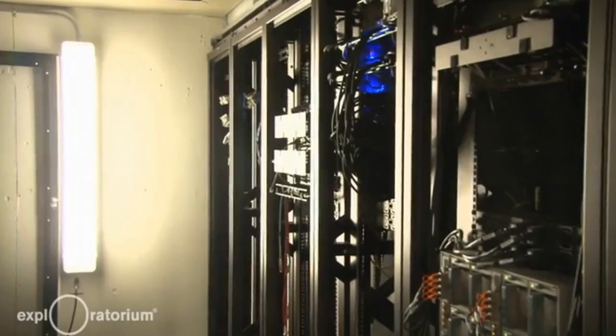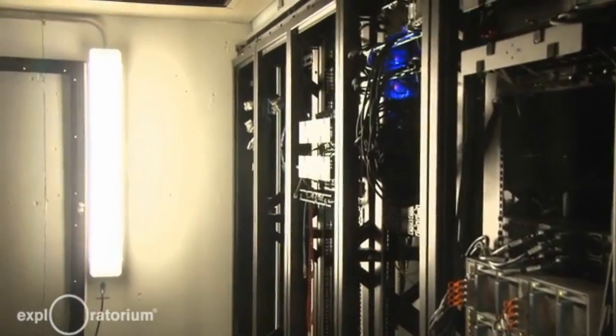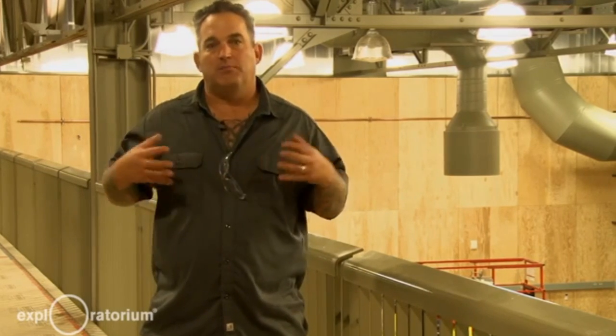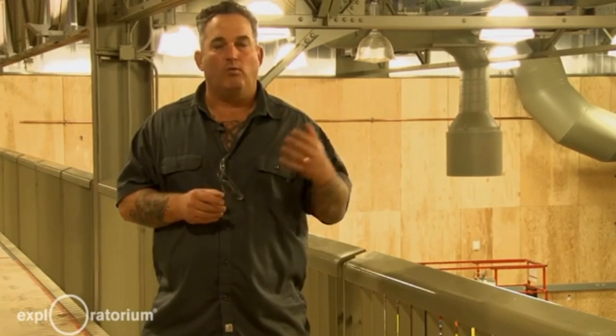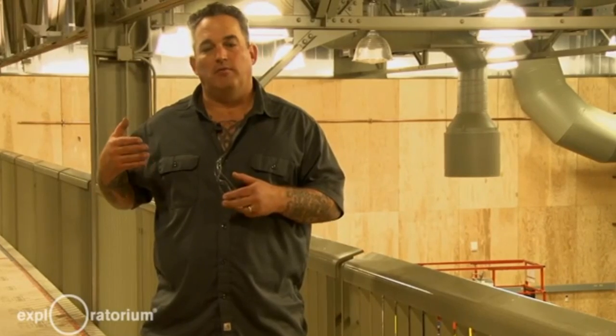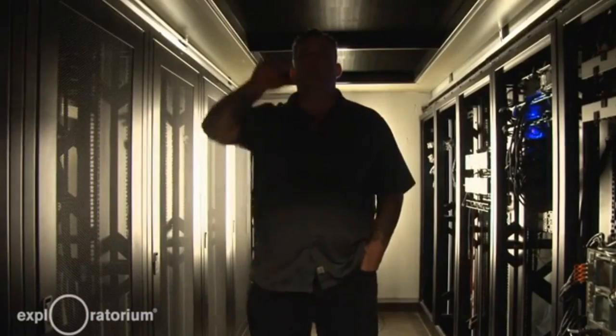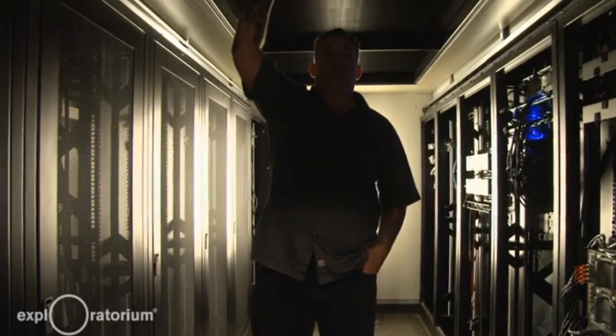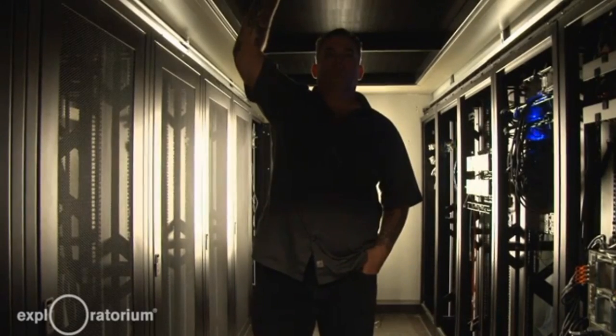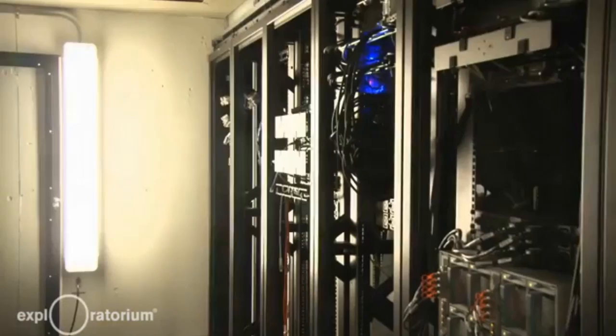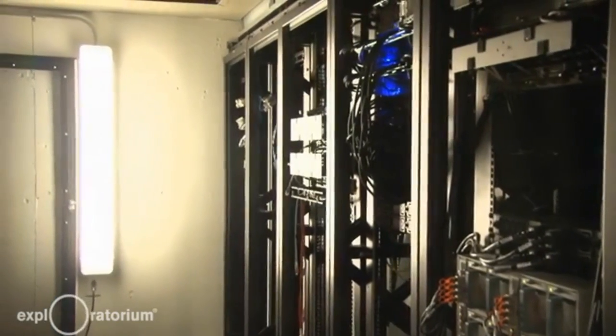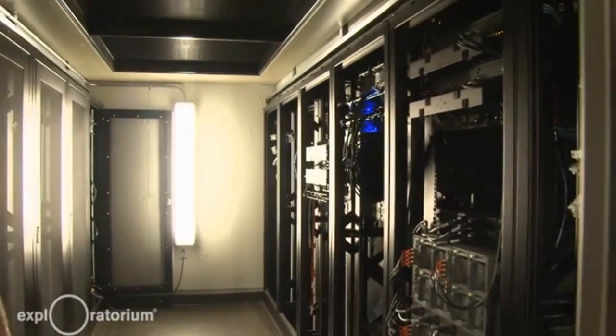The room we were just in is the main server room for the Exploratorium. All five server rooms feed into that one room, the main network point of the whole building. It draws heat from the servers into a hot aisle, which goes up through coils similar to a car radiator, pulling heat from the room and dispelling it back into the ocean—the ocean acts as the heat sink. That's what that room does.